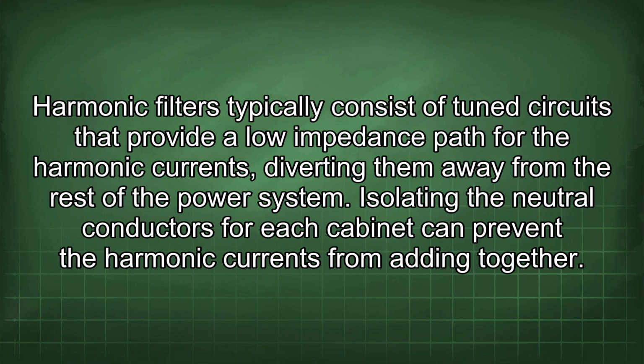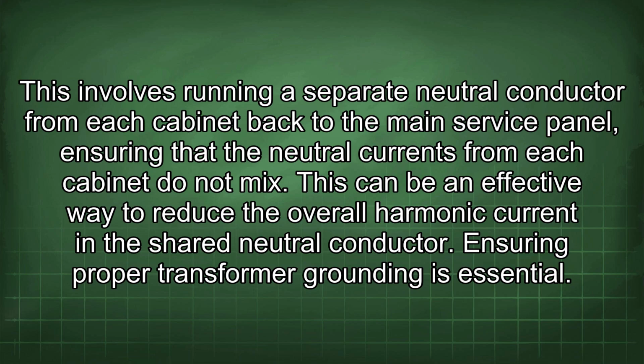Isolating the neutral conductors for each cabinet can prevent the harmonic currents from adding together. This involves running a separate neutral conductor from each cabinet back to the main service panel, ensuring that the neutral currents from each cabinet do not mix. This can be an effective way to reduce the overall harmonic current in the shared neutral conductor.